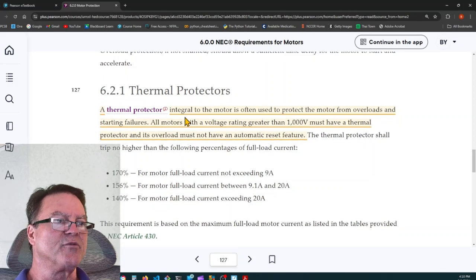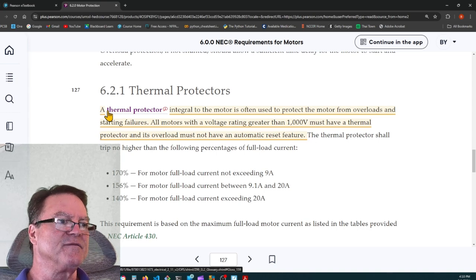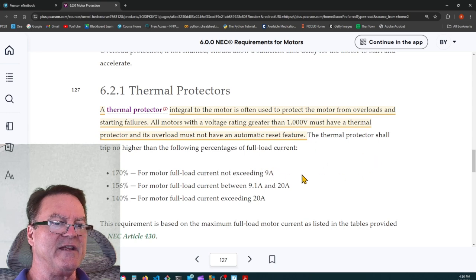Thermal protection. A thermal protector, this is a highlight, integral to the motor, is often used to protect the motor from overloads and starting failures. All motors with a voltage rating greater than 1,000 volts must have a thermal protector, and its overload must not have an automatic reset feature. So thermal is heat. If it's 1,000 volts or greater, you have to have a thermal protector where, if it heats up, it'll trip and open the circuit, and it's not an automatic reset. You have to reset it yourself.